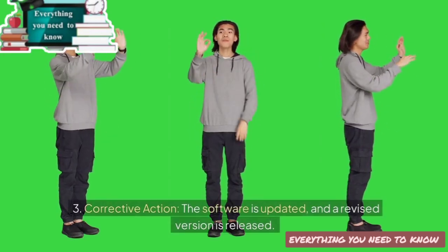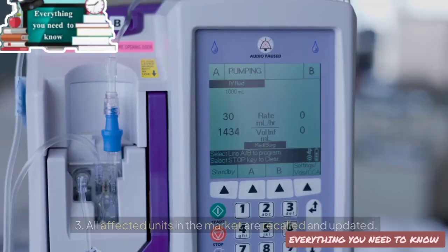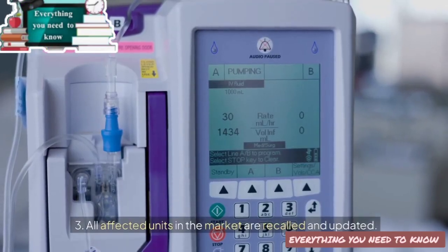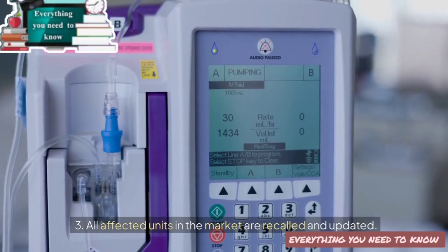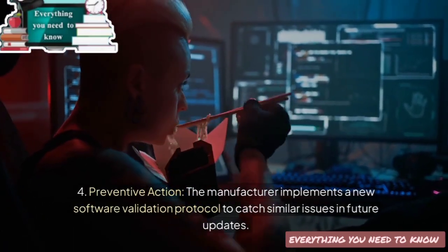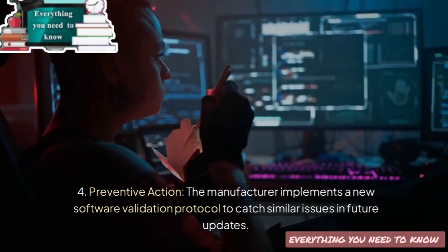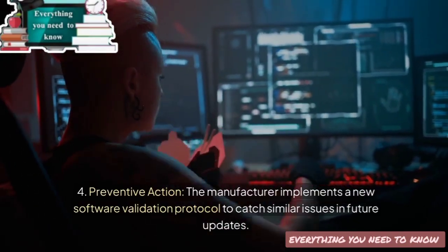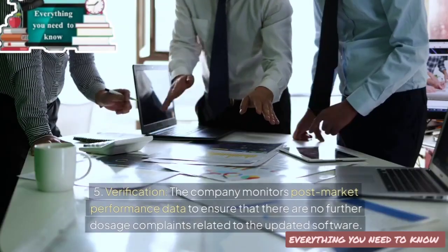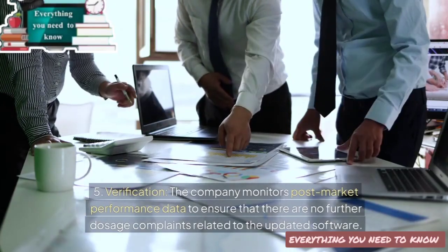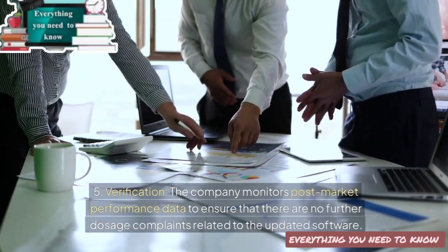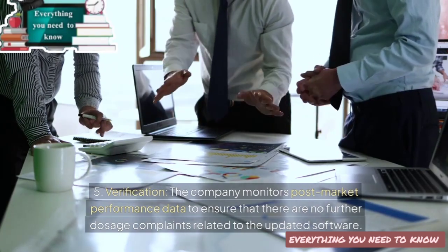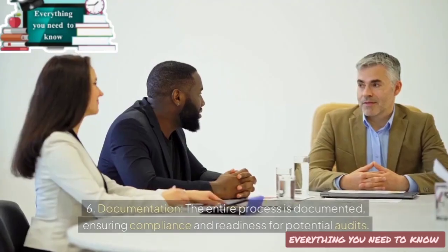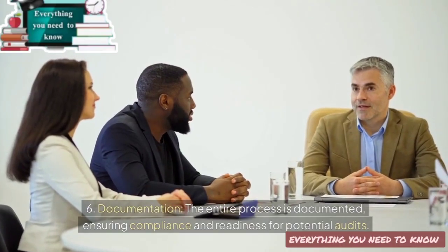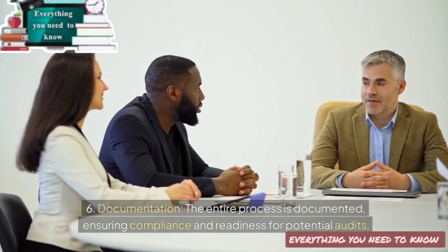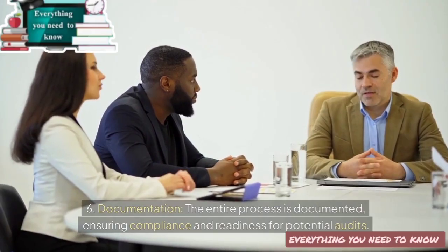3. Corrective action. The software is updated and a revised version is released. All affected units in the market are recalled and updated. 4. Preventive action. The manufacturer implements a new software validation protocol to catch similar issues in future updates. 5. Verification. The company monitors post-market performance data to ensure that there are no further dosage complaints related to the updated software. 6. Documentation. The entire process is documented, ensuring compliance and readiness for potential audits.